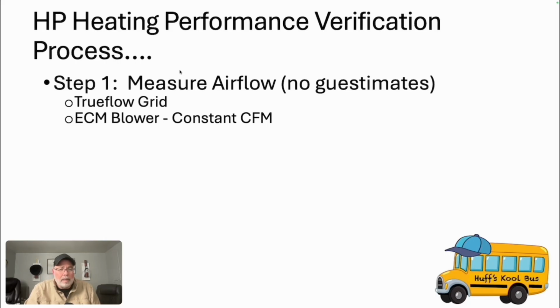But if it is an ECM constant CFM motor, then you can actually go off those airflow settings, whether it be in that communicating thermostat or whether it be on the settings on that board. Some boards will even give you blinking lights to show how many hundred CFM they're delivering. And so that is a fairly accurate method to use, according to the factories that I had worked for.